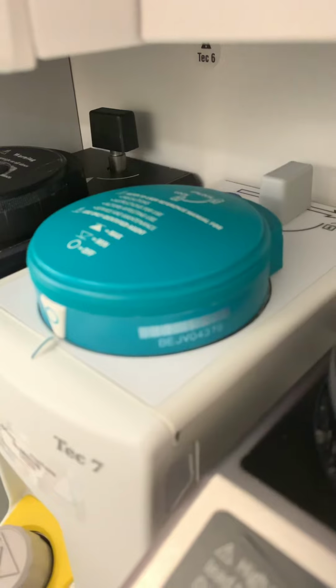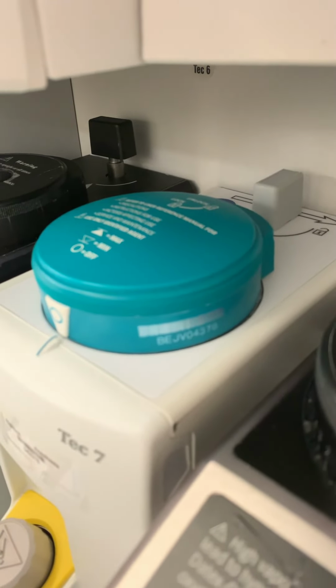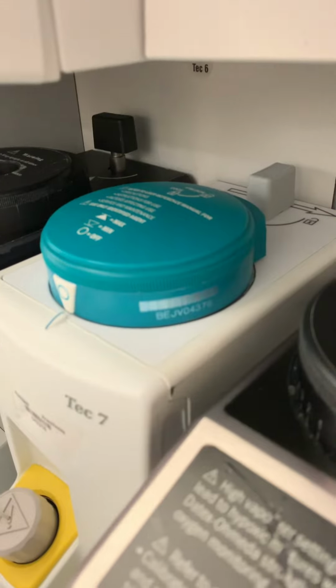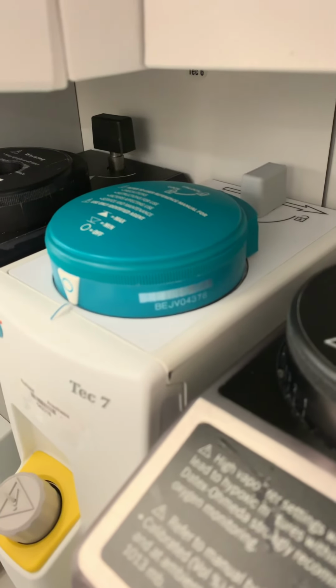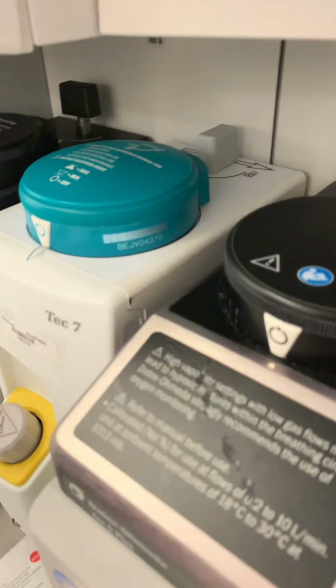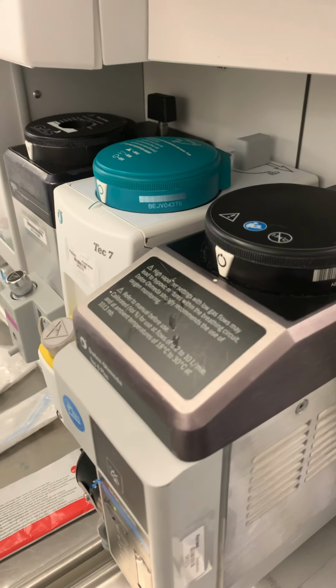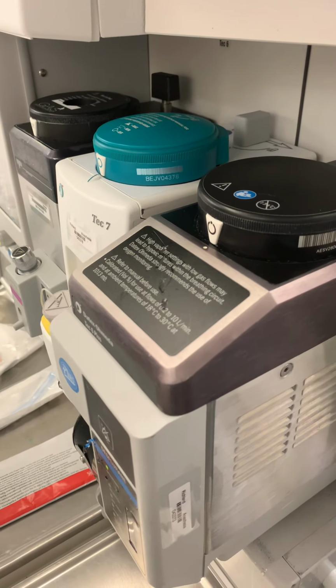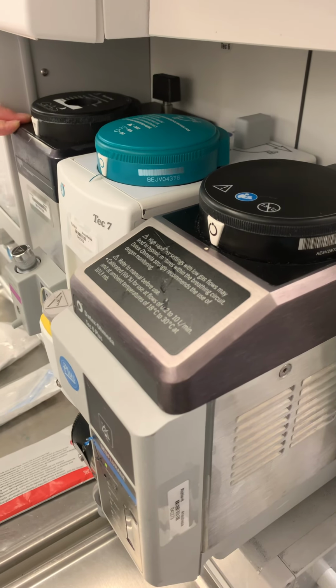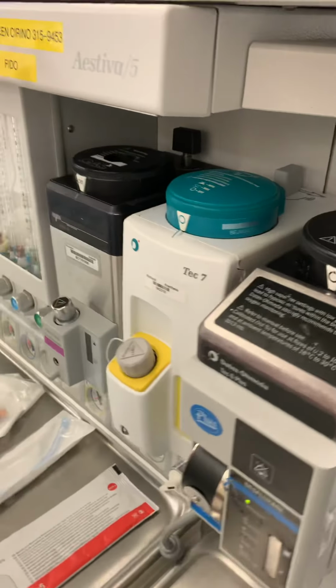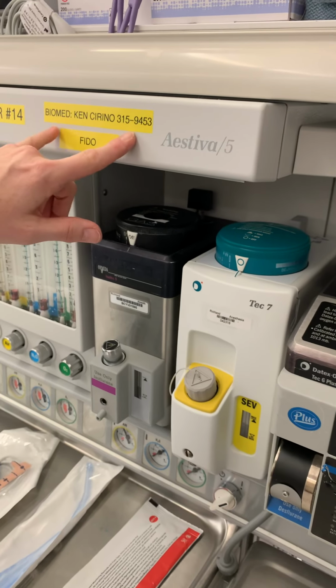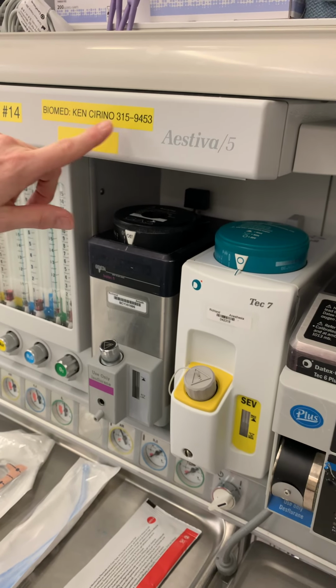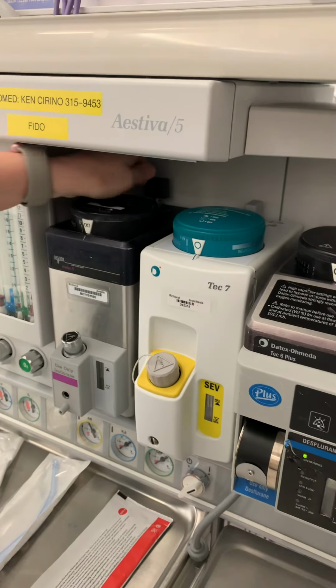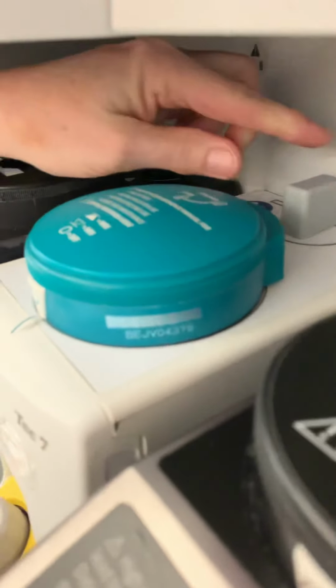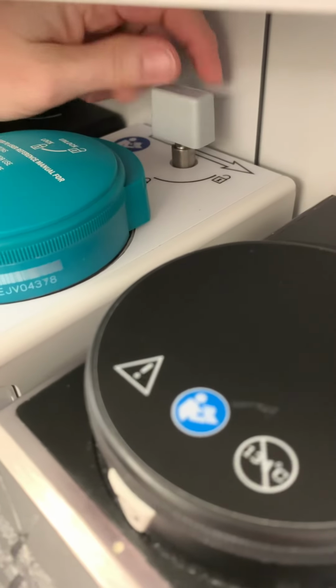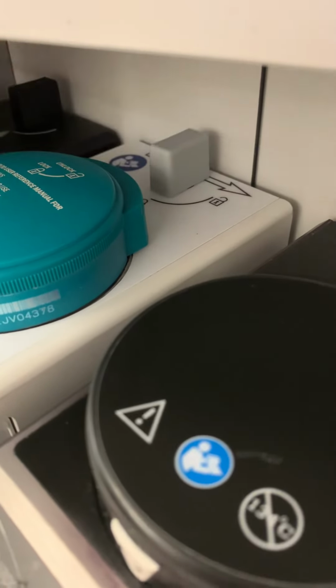If you ever take a vaporizer off the manifold, you have to hold it upright, and just like it is, you can never tip it one side or the other, or God forbid, drop it. I would recommend not taking any vaporizers off the manifold. If there's something that needs to be done, just call our biomed guy, and I'll just use this moment to show you there's a sticker on every machine with the biomed contact and phone number. So let's go ahead and lock this down, and you'll notice everybody's got one that you can lock and unlock.